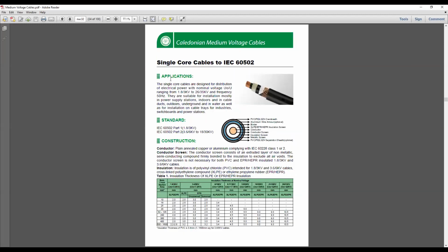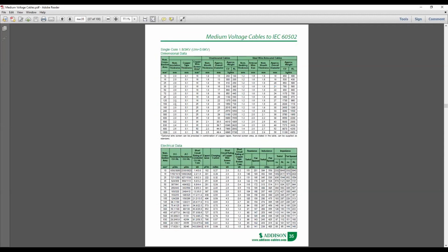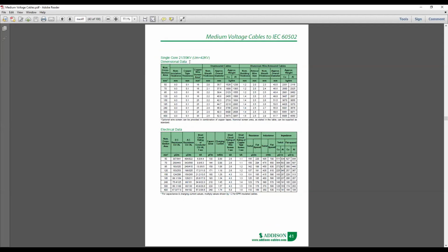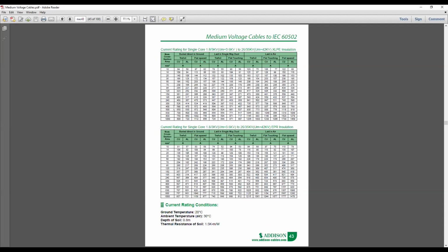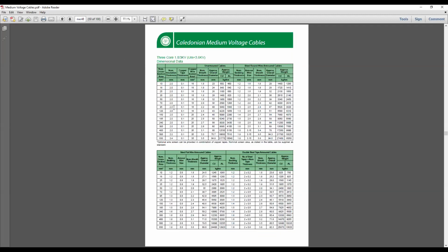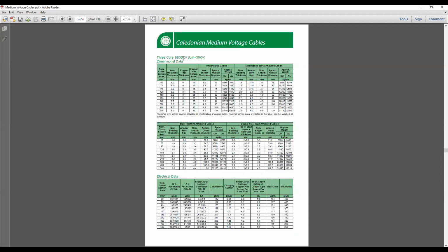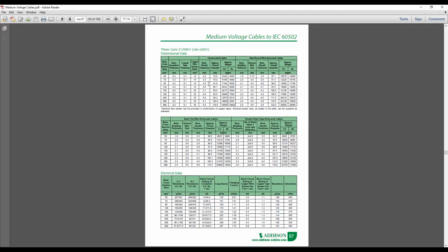Okay. So in here they have included all the details you need to know about these conductors. If you go to the tables, let's go to the 33 kV one. So these are single core. I said we really like 3-core cables when we come to medium voltage designs. Let's go to 3-core cables. So 33. Okay. Yeah. In here we have 3-core up to 35 kV voltages.